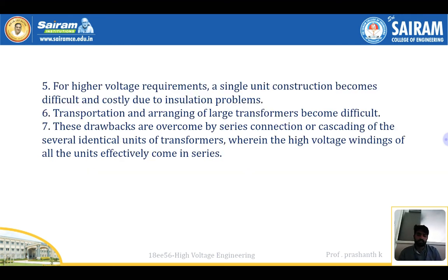For higher voltage requirements, a single phase, single unit construction becomes difficult and costly due to the insulation problem. Transportation and arranging a large transformer becomes difficult, and these drawbacks are overcome by series connection or cascading of several identical units of transformer, wherein the high voltage windings of all units effectively come in series.